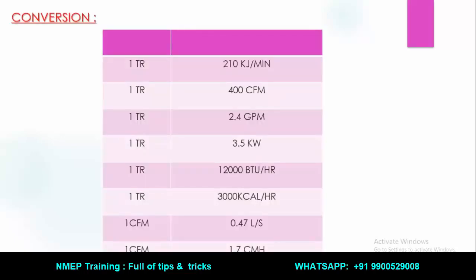It is very important to get all the conversions right. 1 TR is equal to 210 kJ per minute. 1 TR is equal to 400 CFM (cubic feet per minute). 1 TR is equal to 2.4 GPM (gallons per minute). 1 TR is equal to 3.5 kW. 1 TR is equal to 12,000 BTU per hour. 1 TR is equal to 3000 kcal per hour. 1 CFM is equal to 0.47 LPS. 1 CFM is equal to 1.7 CMH.